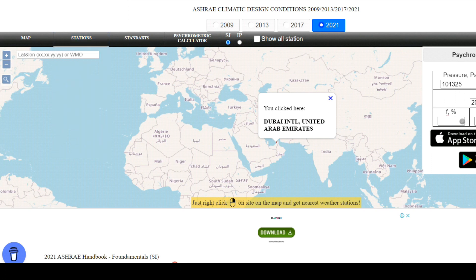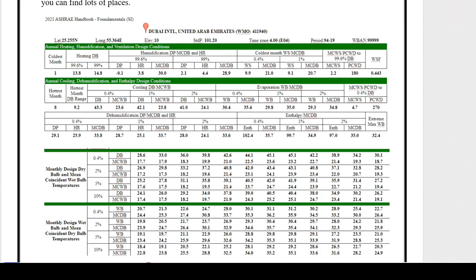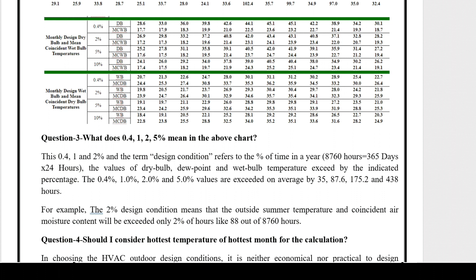If you Google ASHRAE climatic conditions, a page will open where you can see stations. Under Asia, you can select India, Qatar, and other locations. For Dubai, a sheet will appear with important values. You can see percentage values like 0.4%, 1%, 2%, and 5%. There are also monthly design dry bulb with mean coincident wet bulb, and monthly design wet bulb with mean coincident dry bulb. We need to know exactly what to consider — dry bulb with mean coincident wet bulb, or the design wet bulb.